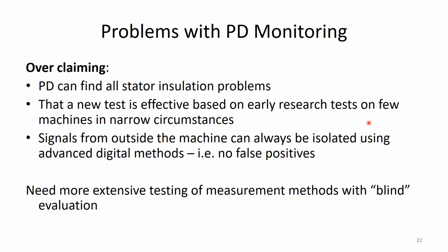It's not true. One, PD can't find all stator insulation problems. I already talked about that. It won't find turn-to-turn issues. It won't find end winding vibration issues until you're further along. An online test will never find problems at the neutral, okay? Unless you want to put a sensor at the neutral. So there are limitations of what PD can do.